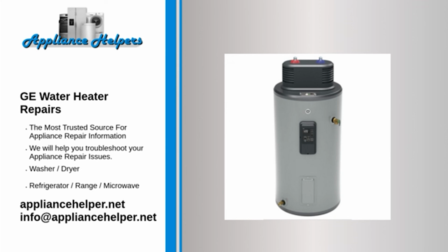Water heater leaking. The temperature and pressure relief valve opens to stabilize the temperature or pressure of the water heater if the temperature or pressure exceeds the proper level. The temperature and pressure relief valve opens at a set temperature. This temperature is indicated on the water heater. If the temperature and pressure relief valve leaks even though it has not reached the indicated relief temperature, replace it.